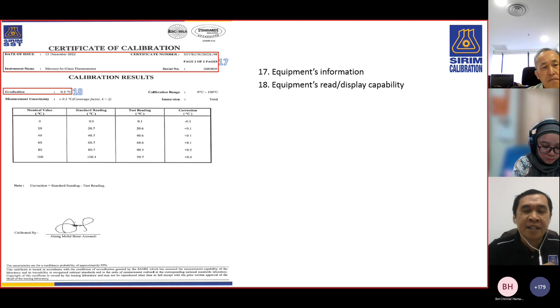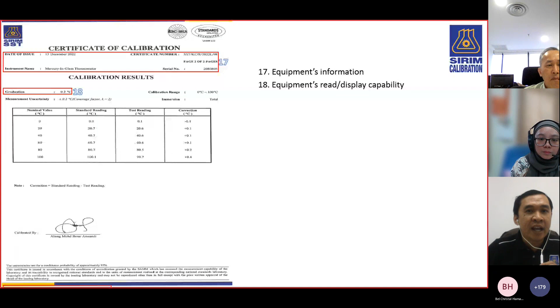Then number 18 is graduation. How much resolution, how many decimals, can your equipment read? It must be stated on every equipment. And measurement uncertainty also needs to be stated there. Please bear in mind that a calibration certificate without stating any measurement uncertainty is not a calibration certificate.